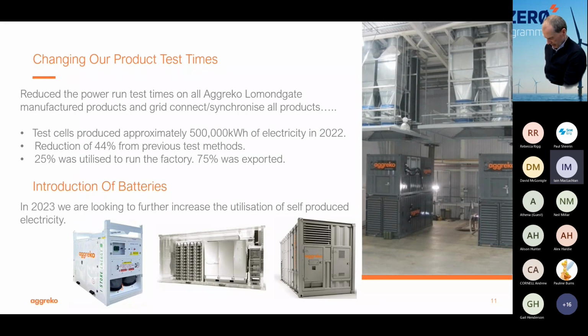We're still only in a position to recognise about 25% of the utilisation to run the factory, and that's based on the fact that the generators we manufacture and test are so powerful. These 1.6 megawatt units are so powerful, and our factory's typical day-to-day consumption is around 350 kilowatts, so they're 4 to 5 times the power our factory runs on. At the moment we're exporting about 75% of what we produce, but we're looking to improve on that by introducing batteries this calendar year.